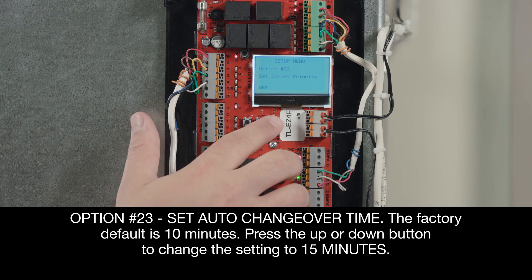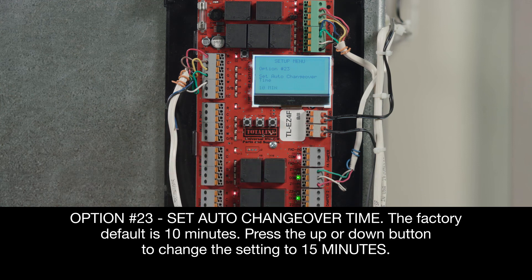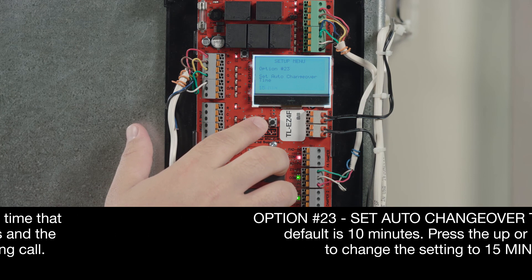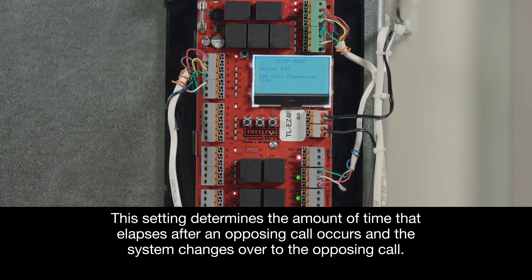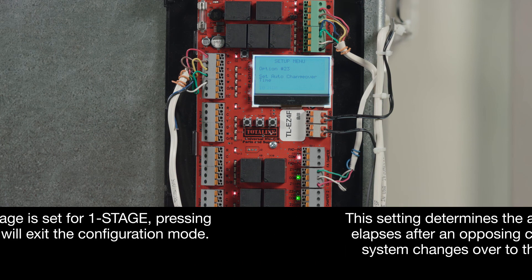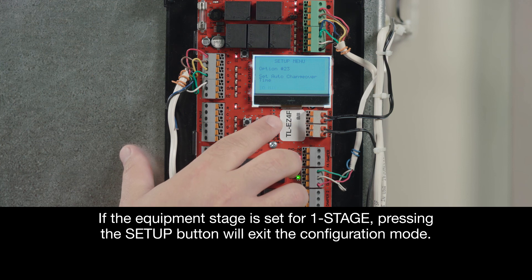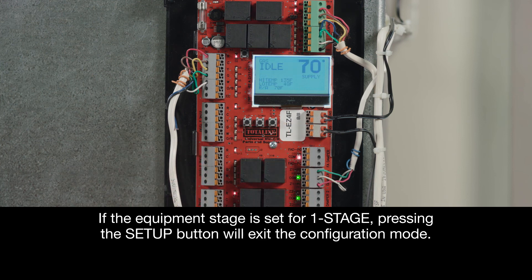And finally, let's go to Option 23, Set Auto Change Over Time. The factory default is 10 minutes. Press the Up or Down button to change the setting to 15 minutes. This setting determines the amount of time that elapses after an opposing call occurs and the system changes over to the opposing call. If the equipment stage is set for 1 stage, pressing the Setup button will exit the configuration mode.